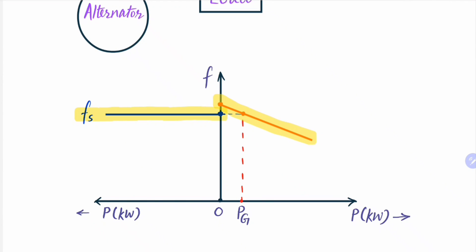For the alternator we know that the fp characteristic will be as shown. The moment when the alternator was synchronized, the frequency of the incoming machine was kept slightly higher than the infinite bus bar frequency. So that the moment when the alternator was connected and synchronized, the point of operation gave a very small power pg supplied by the alternator, because its no-load frequency was kept slightly higher than the system frequency.